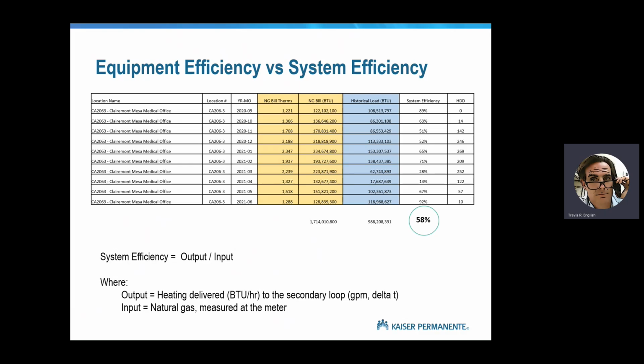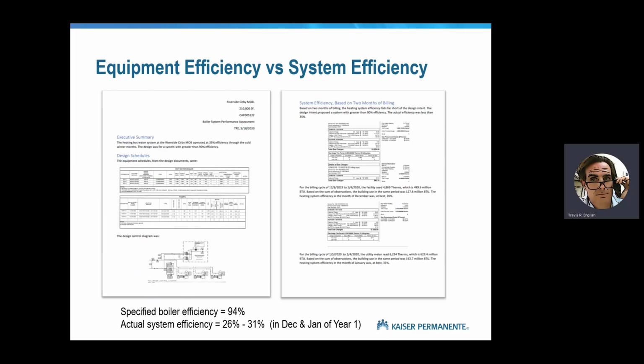You can specify a 90% efficient boiler, but there's also the pumping and the piping and the valving and the gas trains and the flues and the cycling and all these other things that contribute to system efficiency. And system efficiency has to be the overall goal. I told you that story so I could tell you this story, because this is the worst one we've ever seen. I made sure that you can't read the name of the boiler manufacturer here, but suffice to say, this is the most expensive boiler that money can buy. This is a 94% efficient steel tube condensing boiler, right?